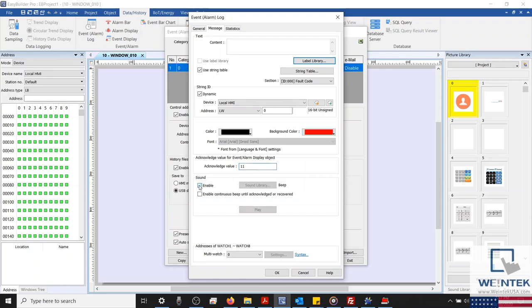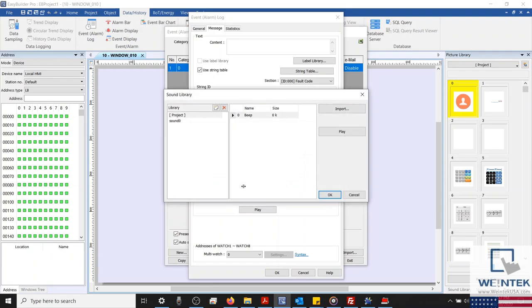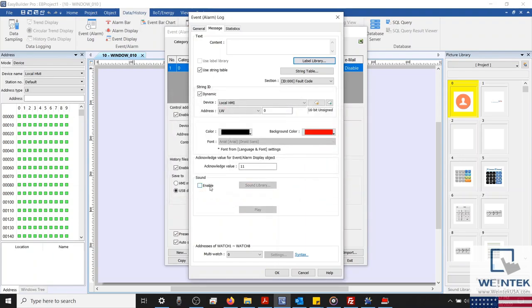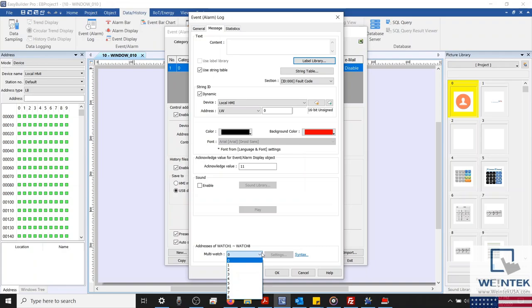Alarms can also utilize an HMI speaker to emit sound. By default, the beep sound is selected. However, some HMIs are equipped with a mono speaker, which can play custom sounds as well. The last feature on this page is our multi-watch function. Multi-watch allows you to create a dynamic message by reading and displaying data from a user-defined list of registers within your alarm's message. This is done by adding the multi-watch syntax to our alarm's message. The syntax can be found by clicking the blue syntax button.